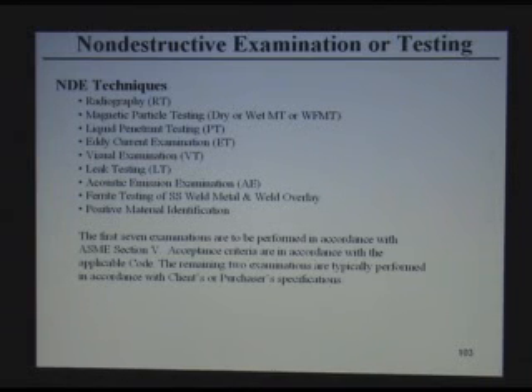Eddy current is another technique, which generates eddy currents, and is useful for the examination of welded heat exchanger tubes, to make sure in mass production that there is no cracking in the tubes. Visual inspection, of course, is very important, and is like 90% of the inspection. The code lists all these things and gives guidelines on how to do them.